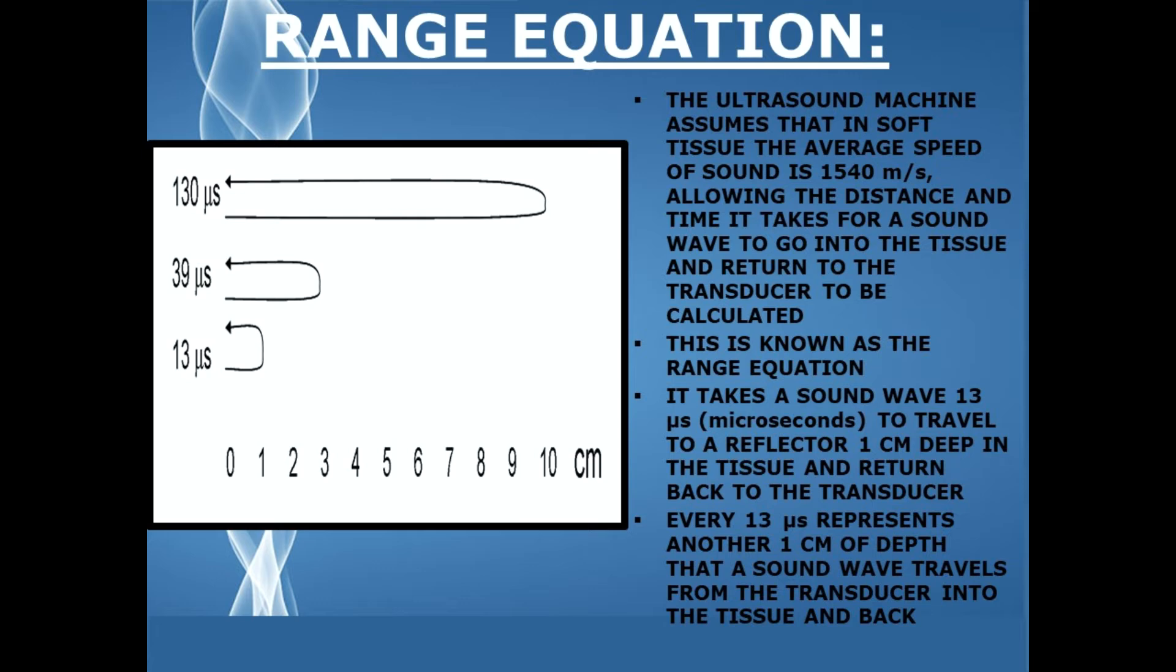Every 13 microseconds represents another one centimeter of depth that a sound wave travels from the transducer into the tissue and back.